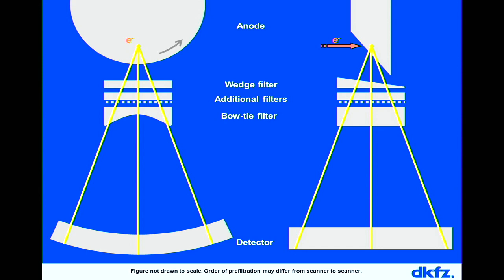Typically today we do spiral CT scans — not just a circle, but the patient is transported through the CT system continuously, called a spiral CT trajectory. Since we also talk about dose, I need to go into the internal design of CT systems. We have a rotating anode; the electrons that hit the anode generate X-rays. The X-rays then run through a series of filters whose most important aim is to remove low-energy photons before they reach the patient, reducing dose.